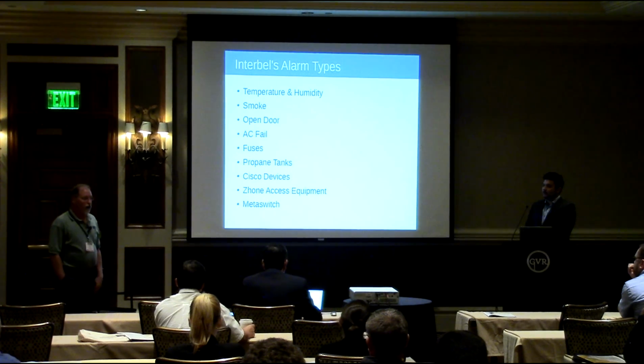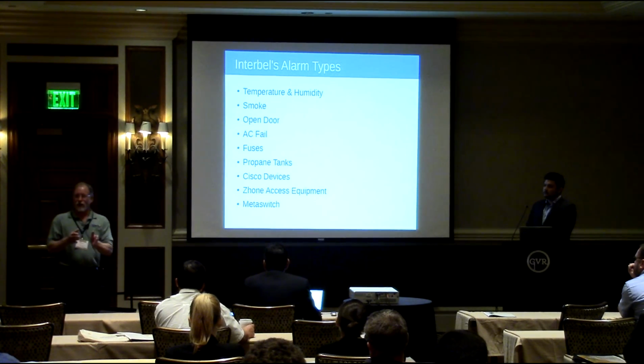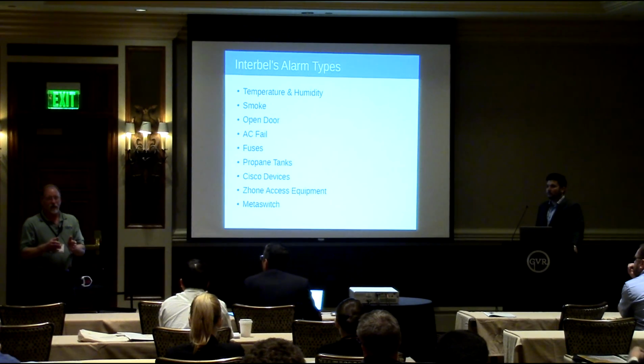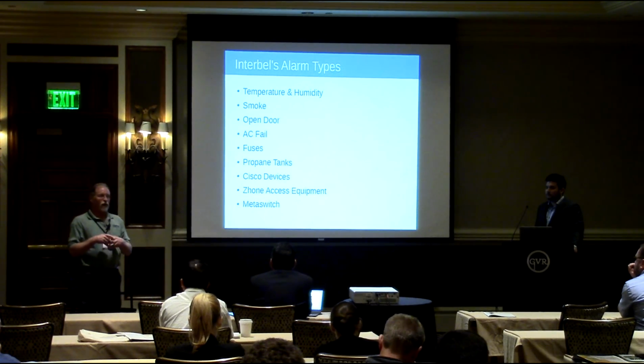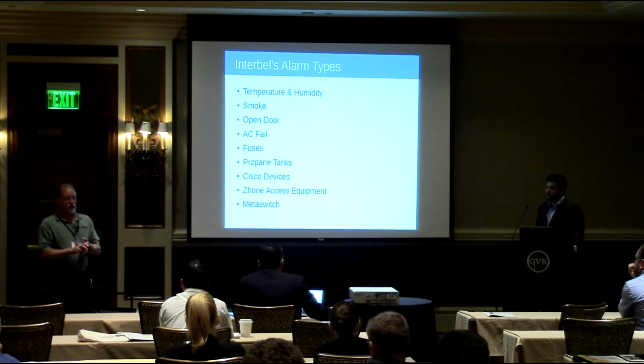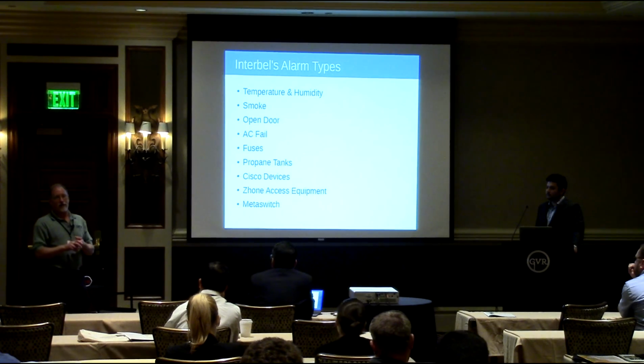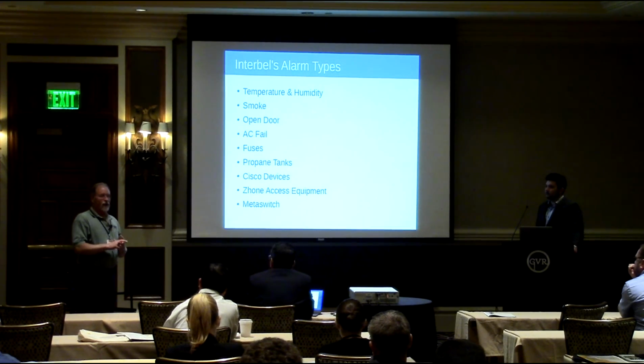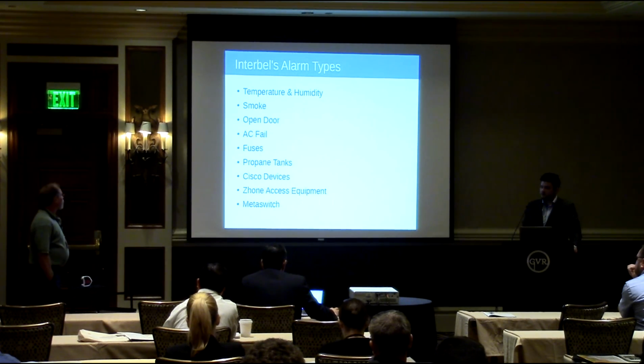We have what they call a network interface device at everybody's home, and we put fiber to it. That network interface device has to be powered, and it has to be powered by AC because you can't line power fiber optics. So in order to power it by AC and still have that ONT backed up, we have to put a UPS in there. And not only do we monitor each one of those NIDs, but we also monitor the batteries that supply power to those NIDs, so we can keep the customer's premise up all the time, because it's very important that the customer has access to 911. And in the event of an emergency, power outage or whatever, that's when they need access to 911. So we have thousands of alarms that we monitor in our system.